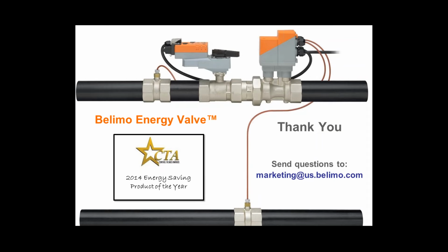Yes, all of the functions for the Belimo Energy Valve are optional, for lack of a better term. So you can switch between the different modes as we saw earlier. We can go from position control to flow control to power control. The Delta T manager can be enabled or disabled. What's actually nice about this function is that enabling or disabling Delta T is a BACnet point, as is the Delta T set point. So if you want to do some advanced programming, you can utilize this function to enable or disable Delta T management based on certain conditions you might see within the rest of your system.